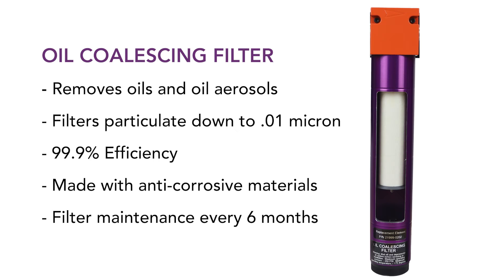The second one is designed to remove your oil aerosols. This would also be considered a major particulate filter that's rated down to 0.01 micron. This is the one that you would have for really critical applications as your last line of defense, just in case there's any old piping particulate that breaks down or any oils that might still be left over in your air system.